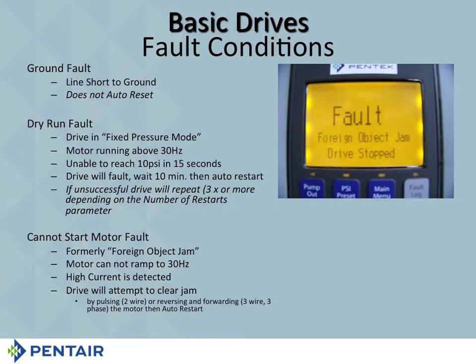Now, the next one we're going to talk about here, there's two types of faults. We call them soft fault and a hard fault. The soft fault is the drive is going to attempt to restart itself. A hard fault means the drive is stopped. When the drive is stopped, somebody must push the fault reset button and then hit the start button again. Of course, you're going to have to fix the fault before you do that, because if you didn't find the fault and fix it, it's just going to jam up again and it's going to fault again.